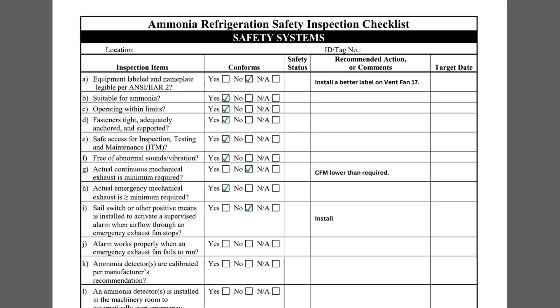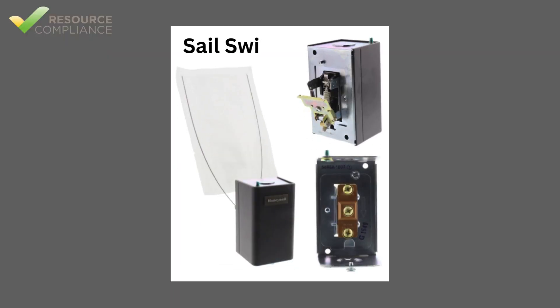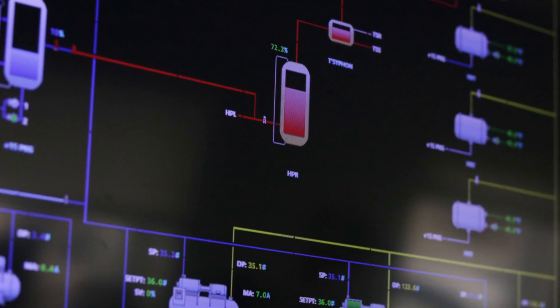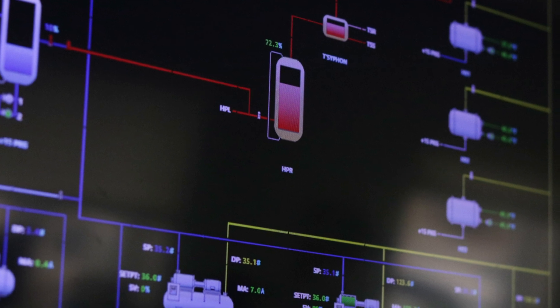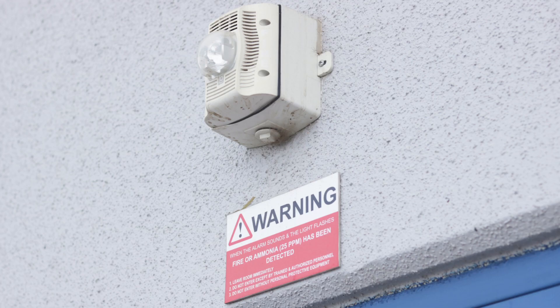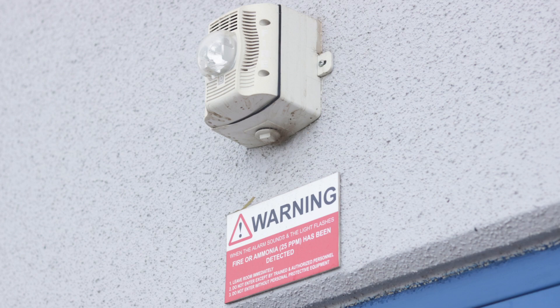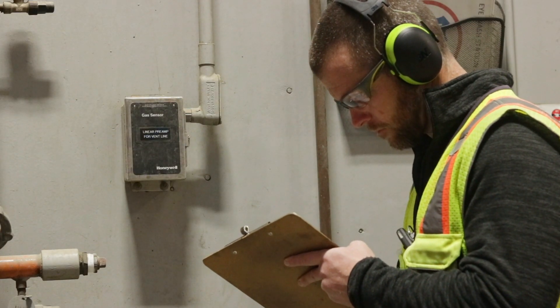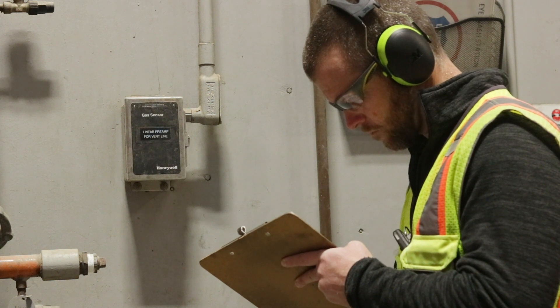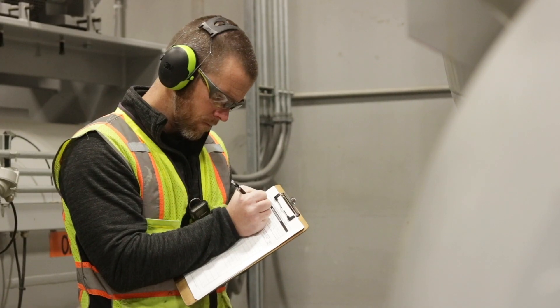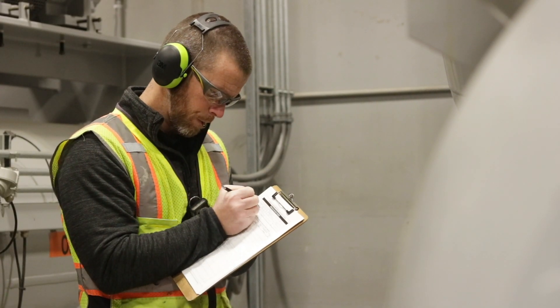Item I asks if the facility has a sail switch or other positive means to activate a supervised alarm when airflow through an emergency exhaust fan stops. This question requires the inspector to determine if the ventilation system is interlocked with an alarm system to notify a monitored location if the ventilation system fails. The facility did not have this interlock in place, so the question should be marked No and a recommendation made. Item J asks if the alarm functions properly when an emergency exhaust fan fails to run. This should be marked No since no such alarm is installed.